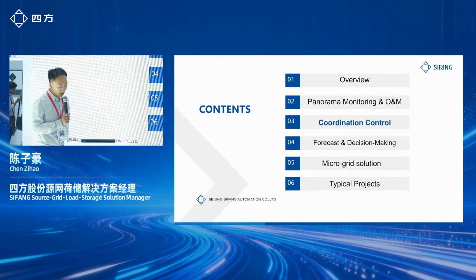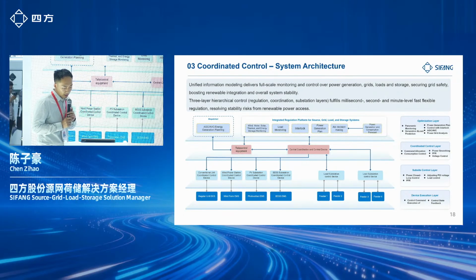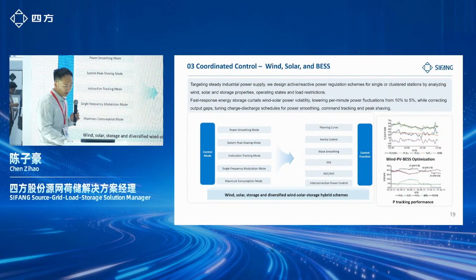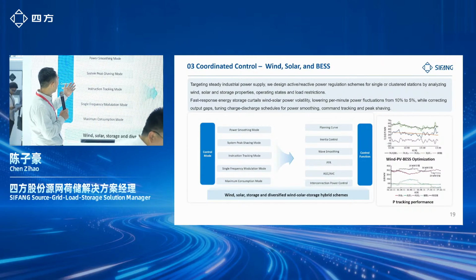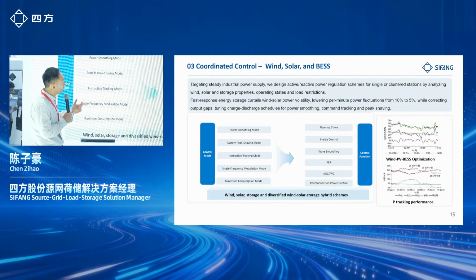And the second module of our solution is very important. It's our coordination control module. We adopt this 3-layer architecture, and we have the optimization layer for the minute level control. We have this coordination control layer for the second level control. Also the substation control layer for the field control. And here is our wind plus solar and BESS coordination module. With this module, we can achieve the power smoothing, also the peak shaving, valley filling, and also we can provide the primary frequency regulation for the fast control.